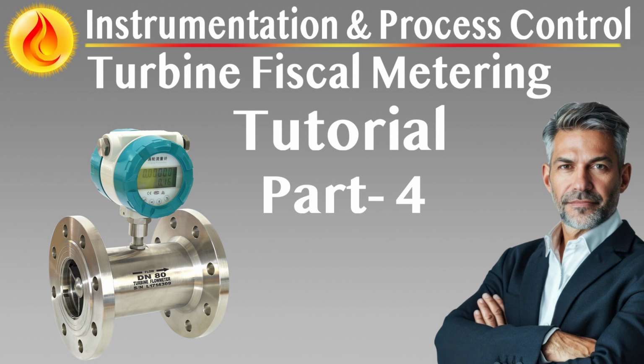Prover microcomputer, automated calibration logic for K-factor validation and sphere control. The Prover microcomputer is responsible for managing all meter proving operations, ensuring that turbine meters are continuously calibrated to traceable standards without interrupting flow. It must operate in conjunction with the stream and station microcomputers and be capable of standalone functionality in case of partial system faults.